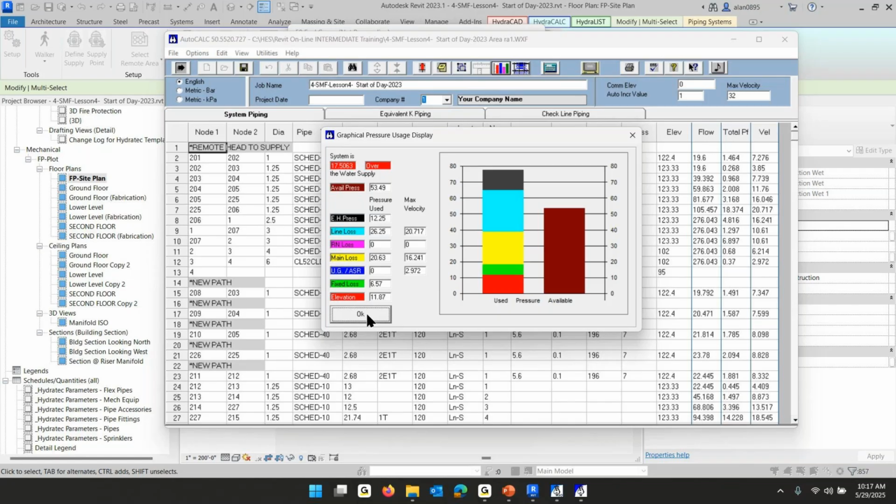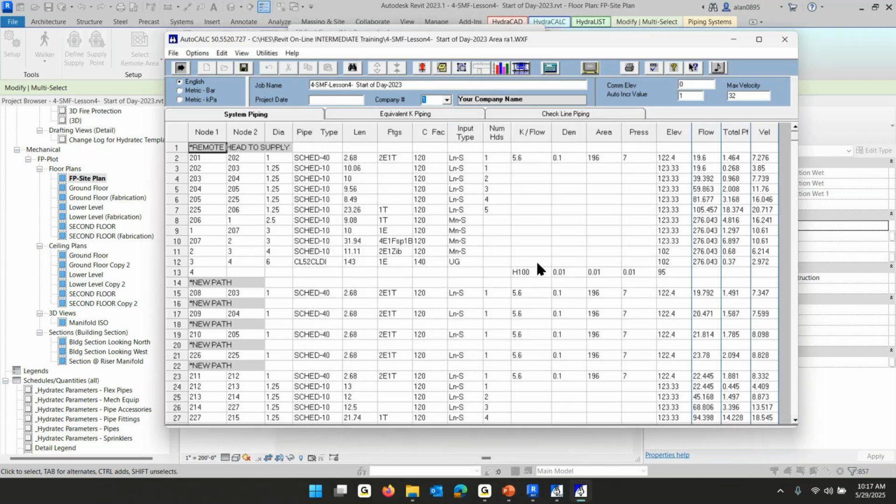However, the other thing I want to remind you of is that we're using 376 gallons a minute. We thought we should only need something a little more than 250. And the reason for that is we simply said none of the heads are spaced any bigger than 14 by 14, so let's just say that they're all at 196. I don't think that's necessary. So I'm going to want to go back and do some investigation on that.